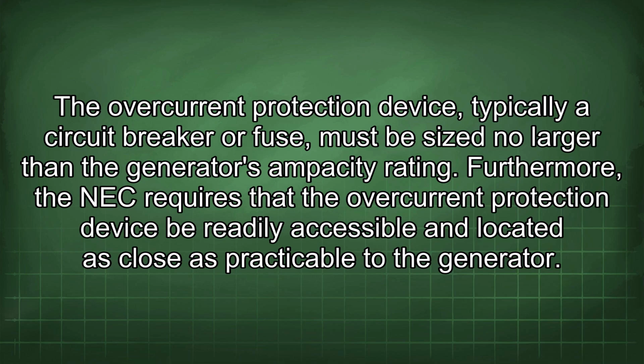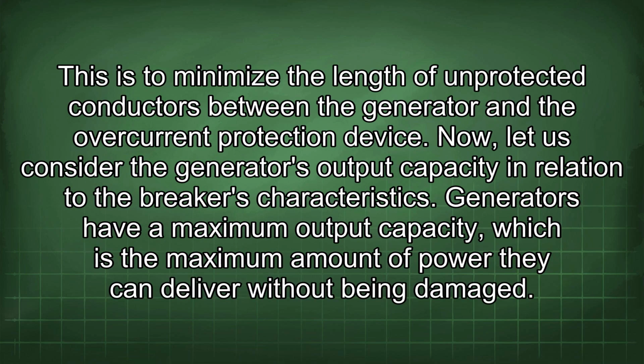Furthermore, the NEC requires that the overcurrent protection device be readily accessible and located as close as practicable to the generator. This is to minimize the length of unprotected conductors between the generator and the overcurrent protection device.